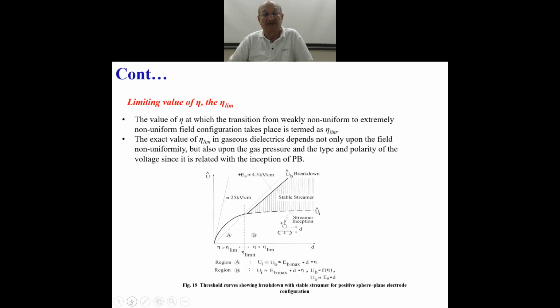The question of polarity of the voltage does come in DC. It does come in lightning impulse or switching impulse also. In AC, it is alternating. So this characteristic is a schematic. We have measured this characteristic also, but let's try to understand from the schematic how eta limit is defined. It shows the peak value applied between the electrodes against the gap distance, which is being changed, measured between a sphere and a plane.